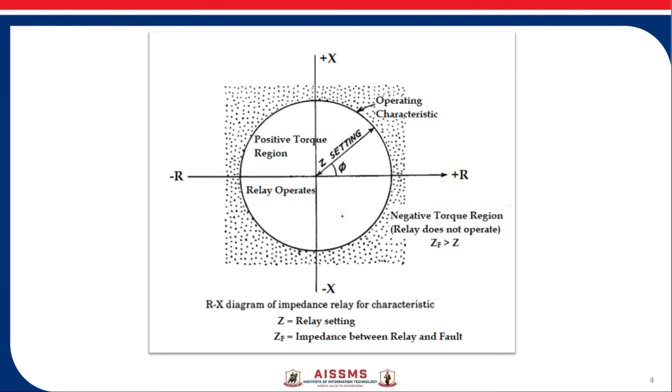RX diagram for this impedance relay: The relay operates for a certain value less than set value of Z. So take Z as a radius and make a circle. The part inside this circle shows the impedance less than predetermined value of Z, and so it is positive torque region and for this region relay will operate.